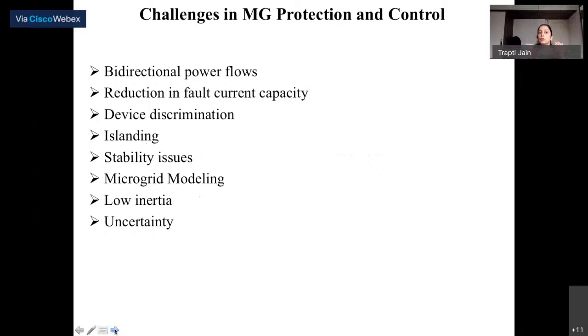It should be able to discriminate the device because the fault current is very less. Then islanding is there. So islanding should be detected very quickly as soon as it happens, because it will not be informed. Now, if it is occurring due to a fault at the PCC point, it will automatically disconnect your microgrid. So if it is disconnecting your microgrid, you should be able to detect that we are operating in islanding mode, and the controller should be able to identify the control strategy so that reliable operation is ensured.